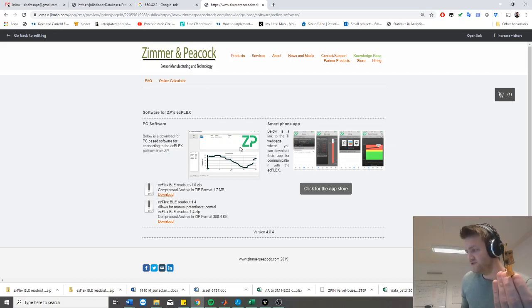And changing the settings can be beneficial if you're running a developmental program. Let's say you have a sensor which is under development, and you're not entirely sure of what the optimal settings are. So it can be advantageous to be able to play around with stuff like dynamic range, gain, internal ground, bias potential, etc. So we're just going to show what the capabilities are.